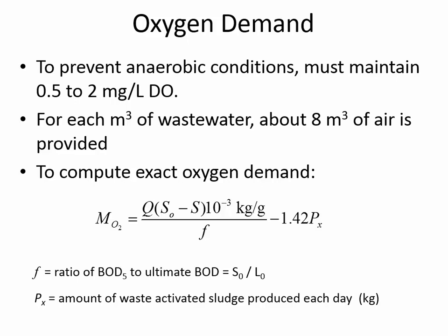And then the difference in S. Why do you think this parameter is in the formula when we're calculating how much oxygen is required? Difference between the inflow BOD and the BOD of the effluent from the aeration basin. How much food they ate. Yeah, if we were going to put a name on what's in the brackets there, we'd call that how much food they ate. And how much food they ate has a direct one-to-one correlation with how much oxygen they need.